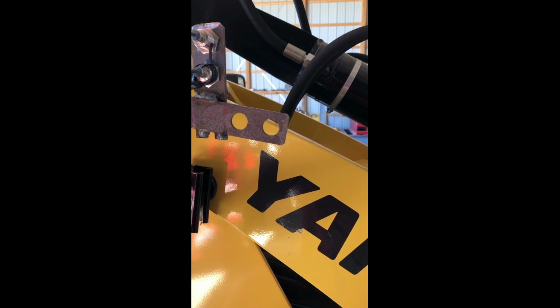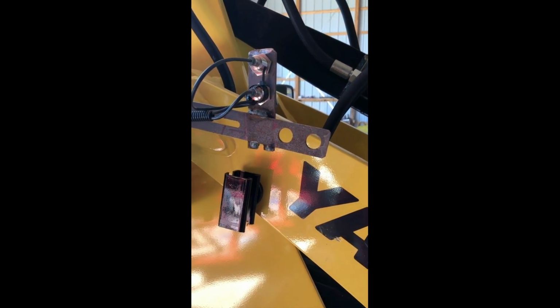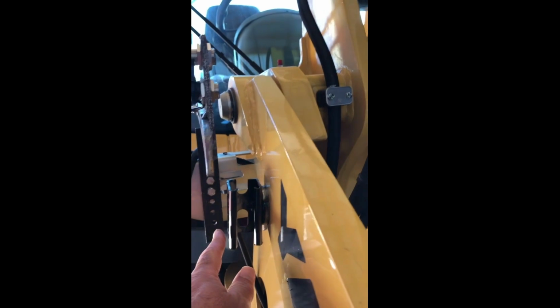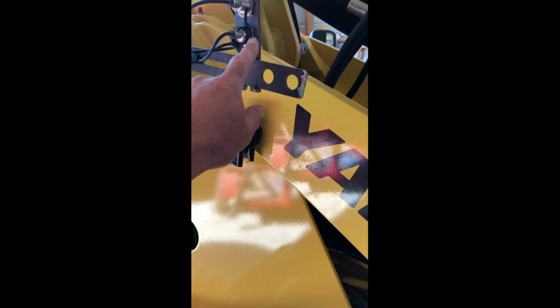Okay, you can see our proximity switches and our target. This is our target that goes by the proximity switches. The proximity switches need to be within approximately 4 millimeters from the face of the switch to the face of the target. The bottom proximity switch will be called proximity 1. The top one will be called proximity 2. And then when your back pin is level with your front pin, your bucket pin down here, when those are level, the top of your target should be at position of the proximity switch number 1 to start the weighing process.